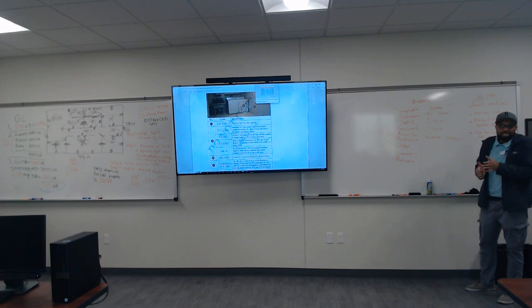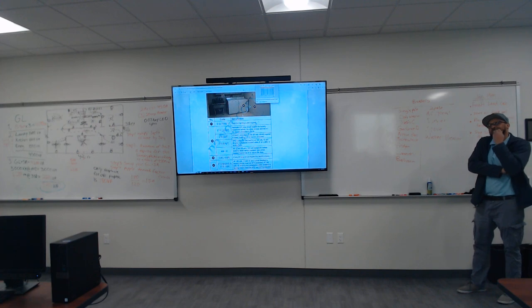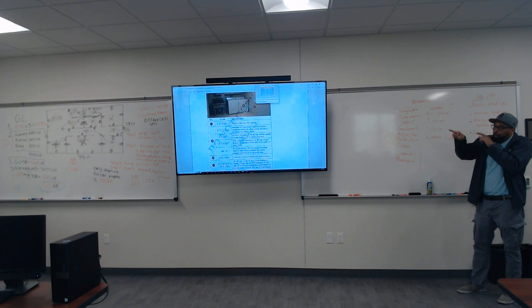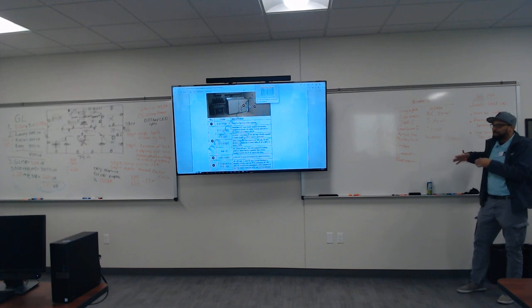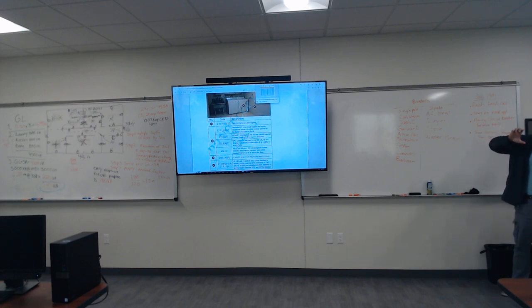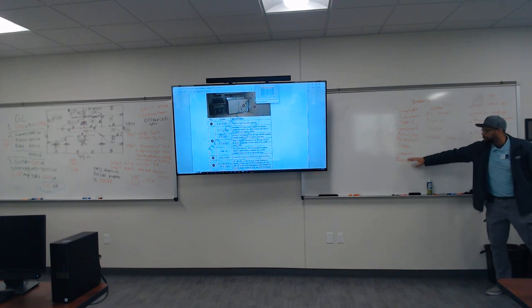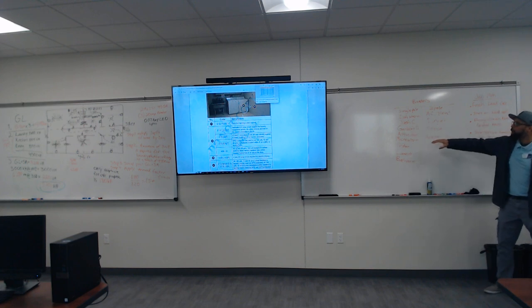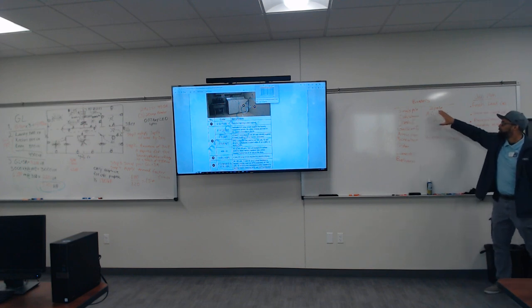So therefore, when you got 16 spaces left, you figure out, can you dissect it more than the four quadrants that I'm about to do? Yes, because you got 16. We already accounted for the double pole breakers, right? And typically, I forgot to also say this. On the double pole breakers, you want to group them, all right? You don't want to spread them out and have them mix and match. You always want to group them. If they're going to be on the left-hand side, make sure they're at the top left. If they're on the left-hand side at the bottom, make sure they're at the bottom. But you always want to start off like you read, top to left, okay?